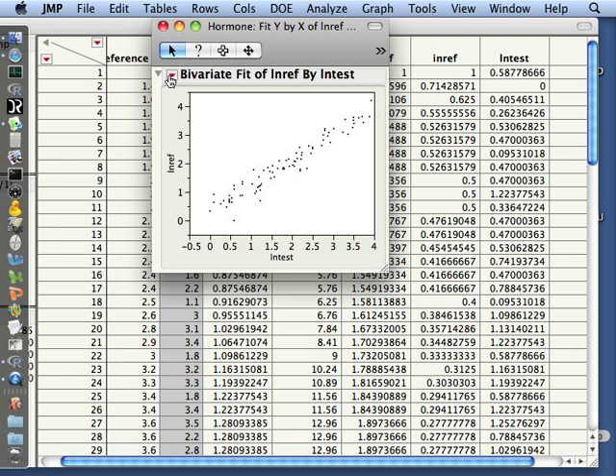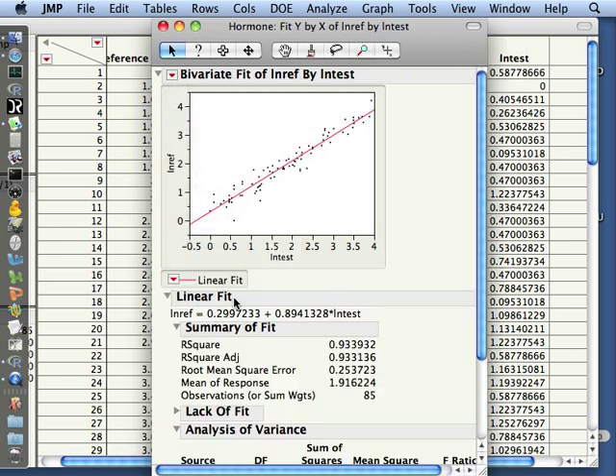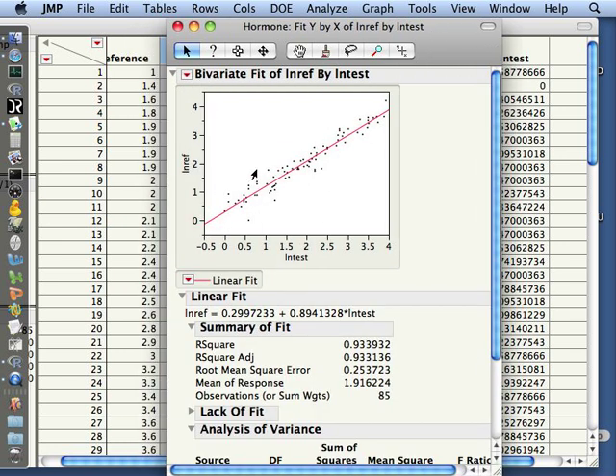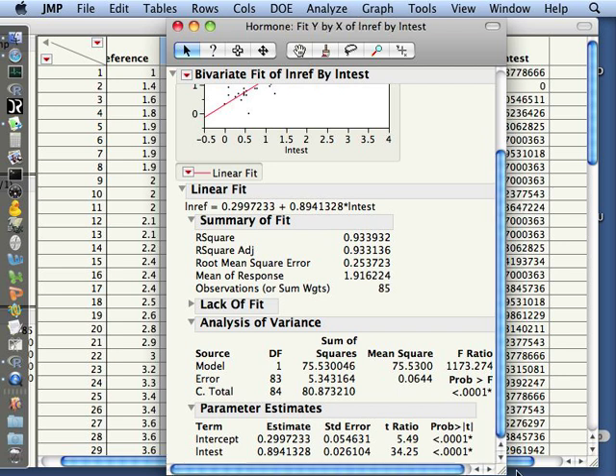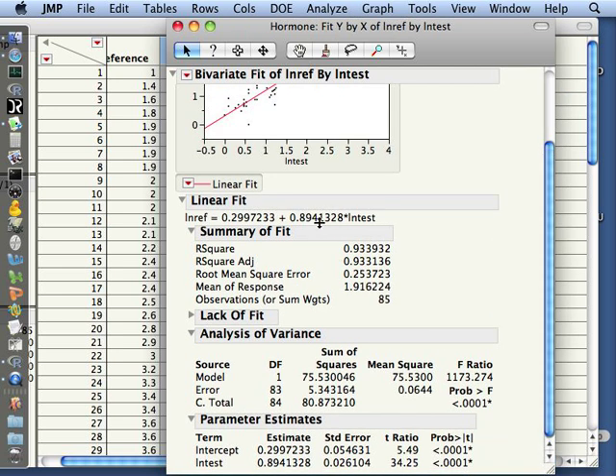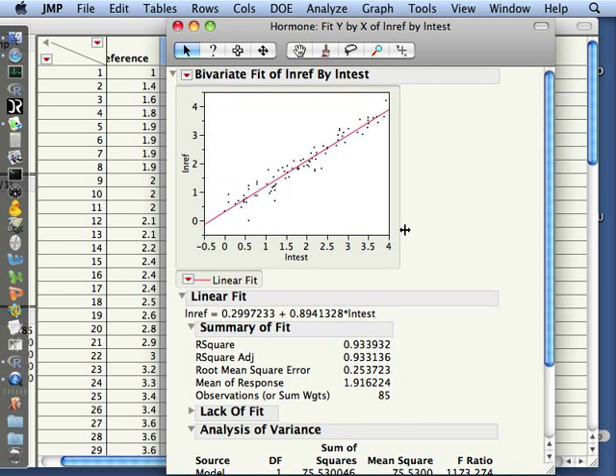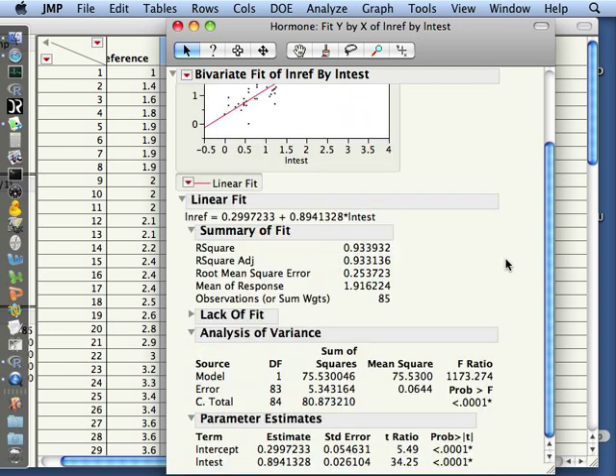This looks actually very similar to a proper good linear regression with a scattering of a random scattering of the line, points around the line. Our r squared has gone up from 91 to 93. The slope has actually gone down a little bit, so it is showing actually a slightly greater difference between the test and the reference. But we do have a valid regression now. And as you can see, the p-value for the slope is definitely positive, so definitely greater than zero.